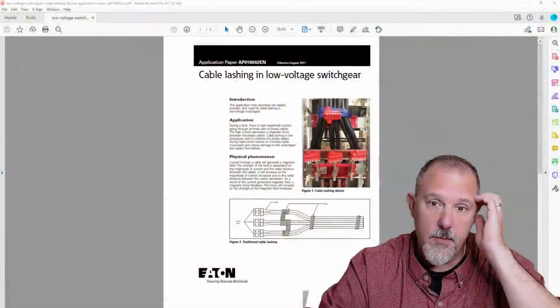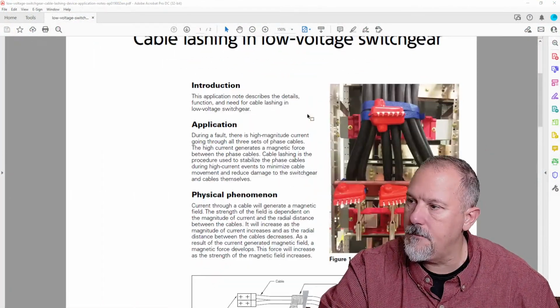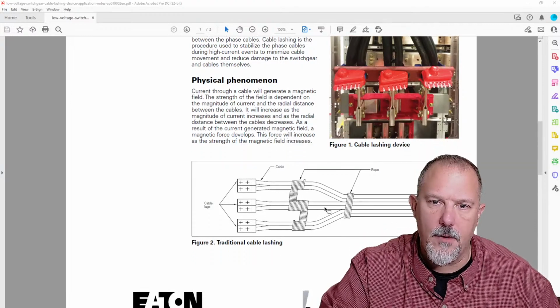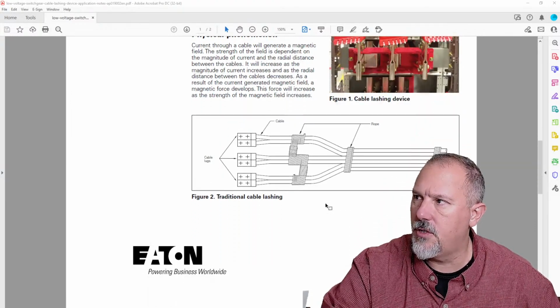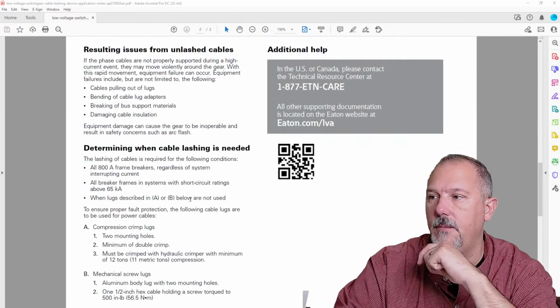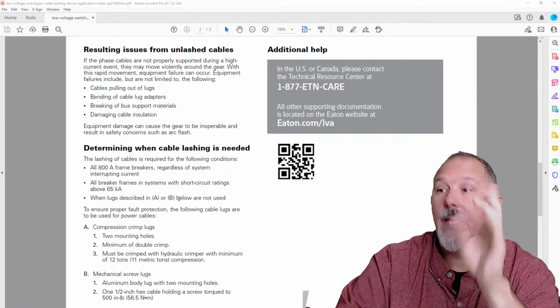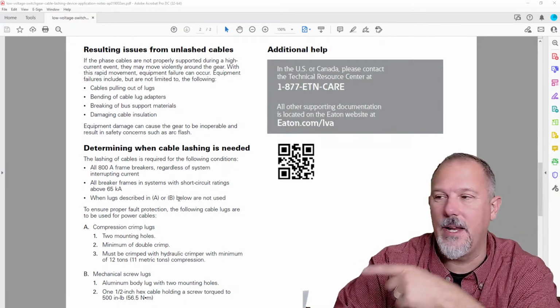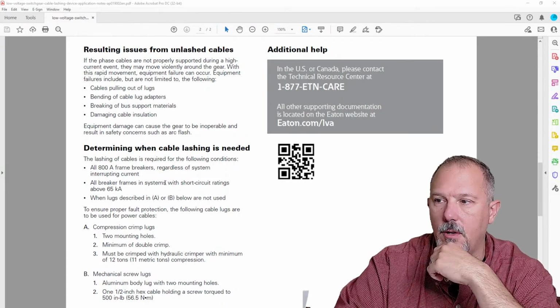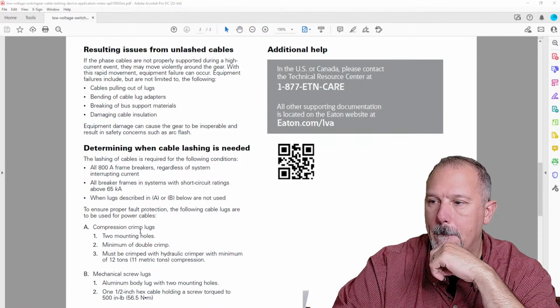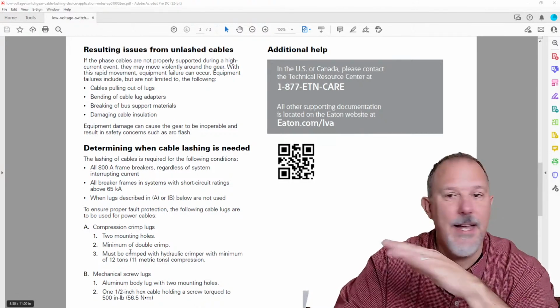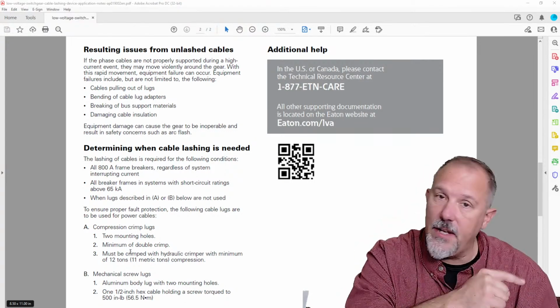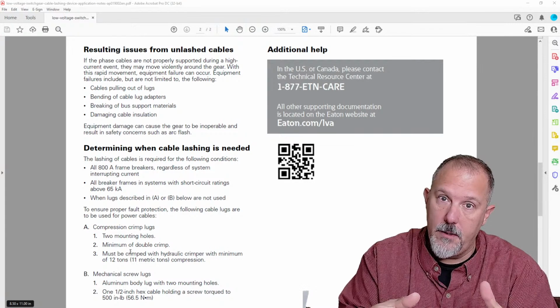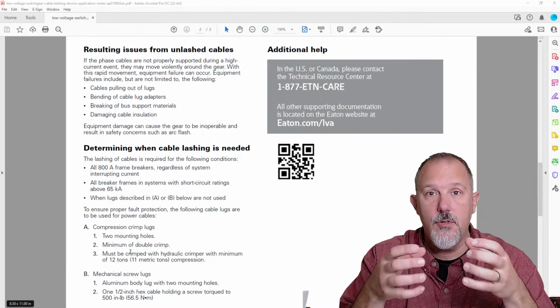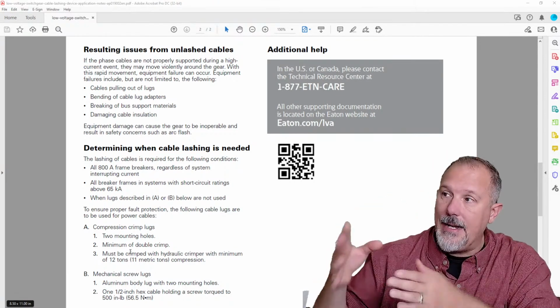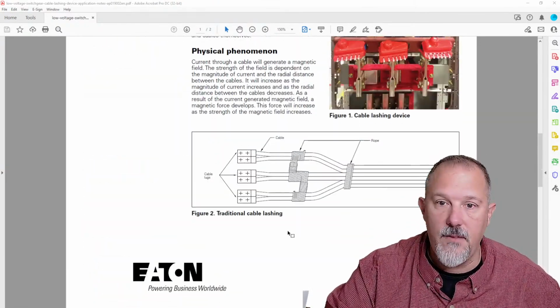So we do have guidance on lashing. Remember this document: cable lashing in low voltage switch gear. We talk about how it's tied with rope - that's traditional. Look, all breaker frames and systems with short circuit current ratings above 65,000 amps, regardless of system interrupting currents, when you have compression crimp lugs with 2 mounting holes - all of this is directly associated with that cable whip video I showed. Because of those magnetic forces, we want to keep those conductors under those lugs, and we have guidance on that in this document.